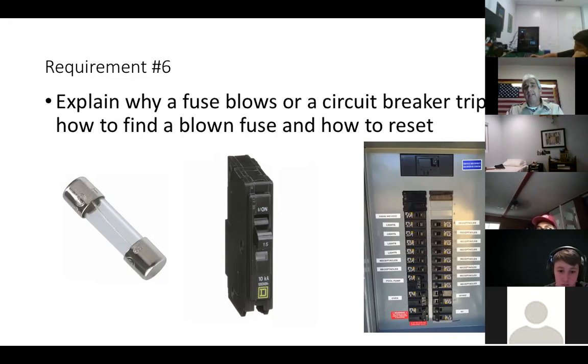That protects your wires, because wires are rated at different thicknesses. It goes from 16 to 14 to 12 to 10 to 6. 16 seems like it would be the highest, but it's not, it's thinner. As you go down, all the way to 0, which is aught, the wire gets pretty thick. Back to the freeway analogy, your wire only makes room for enough of those electrons to flow through. So that breaker's job is to pop when you're pulling way too much.